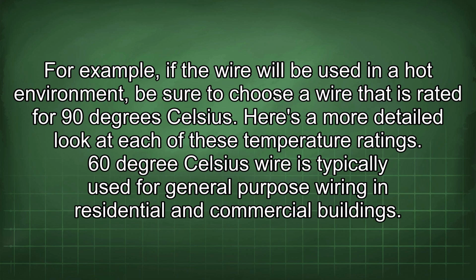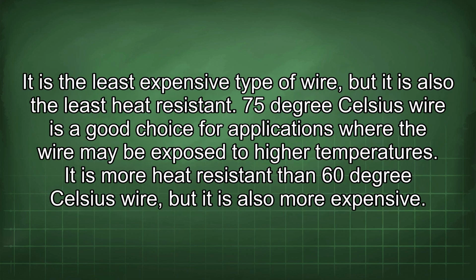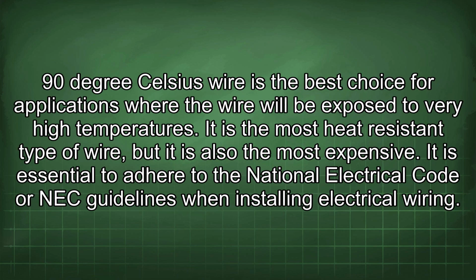60 degrees Celsius wire is typically used for general-purpose wiring in residential and commercial buildings. It is the least expensive type of wire, but it is also the least heat-resistant. 75 degrees Celsius wire is a good choice for applications where the wire may be exposed to high temperatures. It is more heat resistant than 60 degrees Celsius wire, but it is also more expensive. 90 degrees Celsius wire is the best choice for applications where the wire will be exposed to very high temperatures. It is the most heat resistant type of wire, but it is also the most expensive.